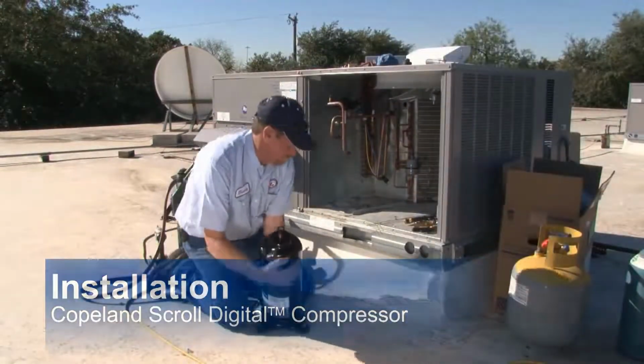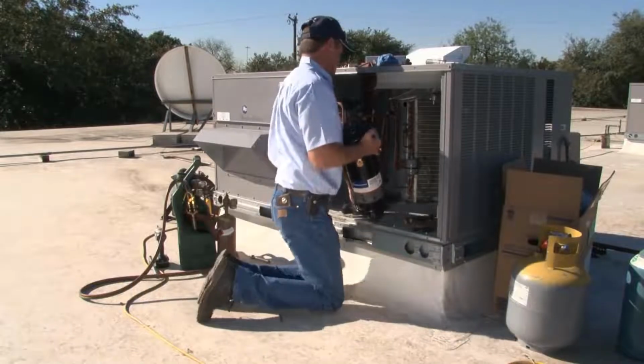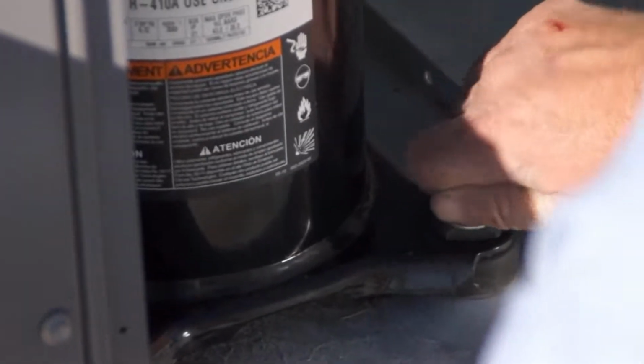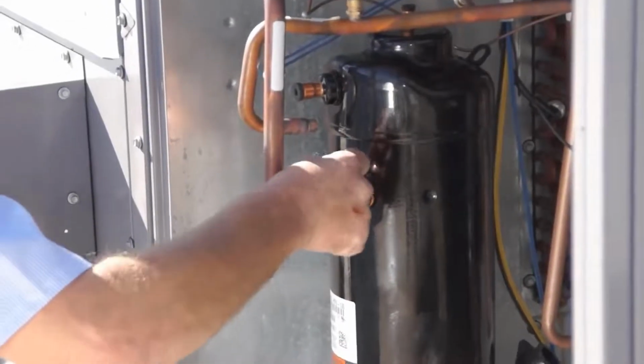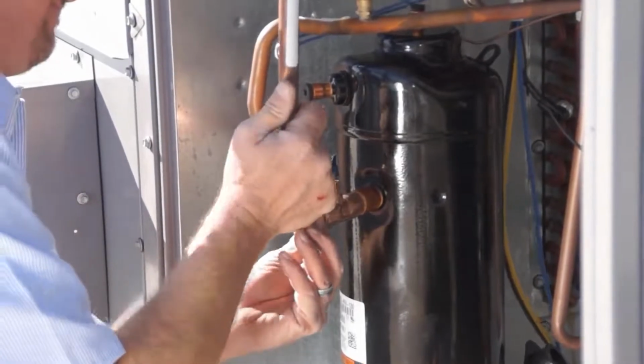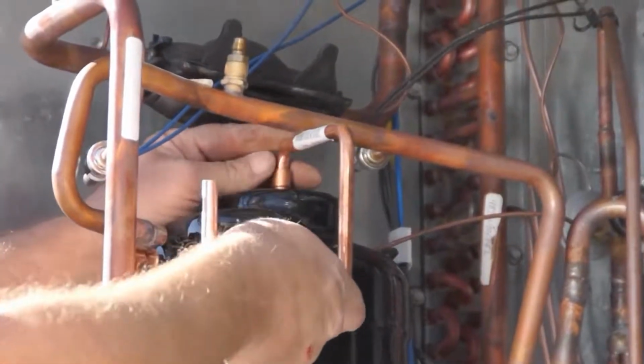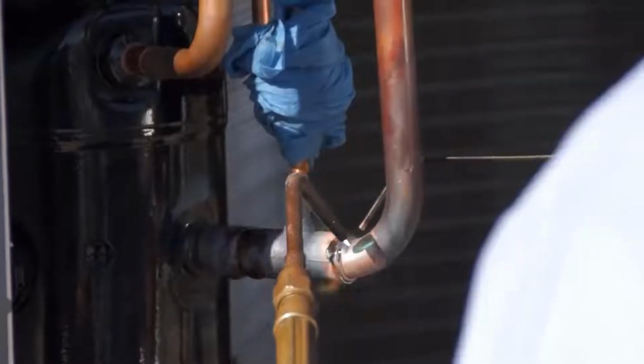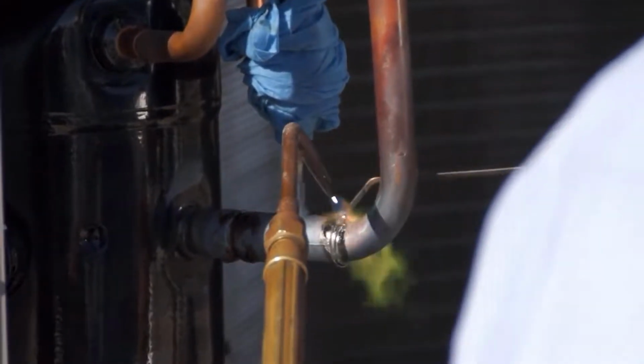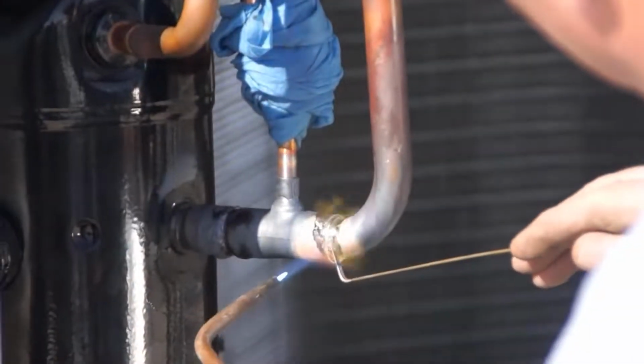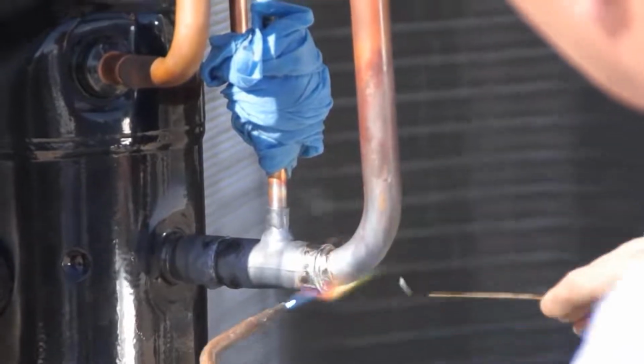Begin the installation of the new compressor by first setting it in place and inserting the mounting bolts. Fit the new copper tubing and valve in place and adjust the lengths as needed. After ensuring proper fit, braze in the new copper tubing. Make sure the new valve is protected from the heat of brazing. A wet rag is commonly used.